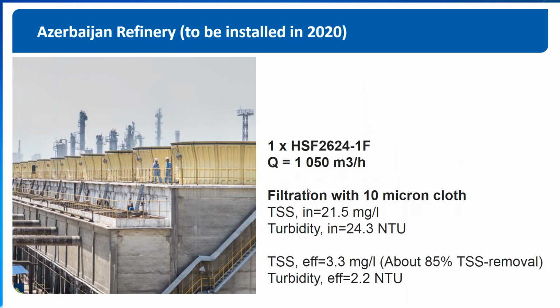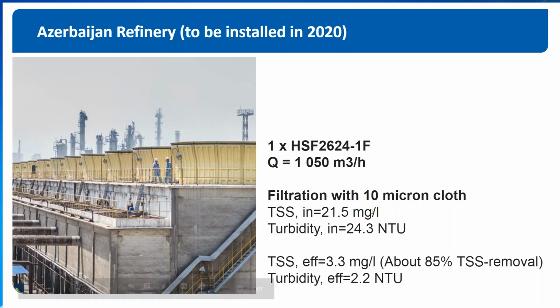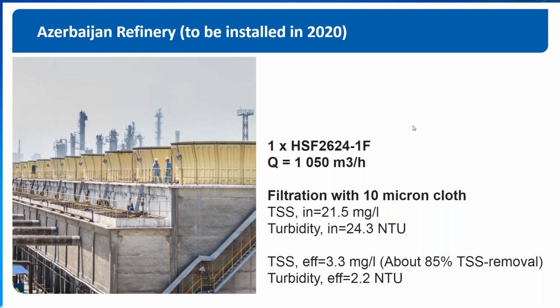Another project is a refinery in Azerbaijan with one filter for sidestream filtration. Here, the 10 micron cloth takes a TSS of 22 milligrams per liter down to 3.3 milligrams per liter. And this is mostly dust and sand, which is contaminating the water.